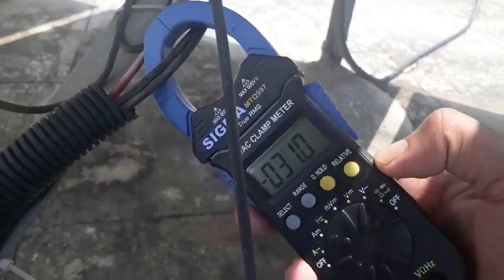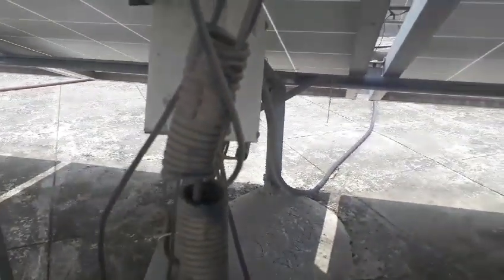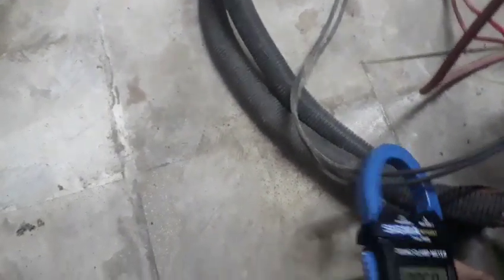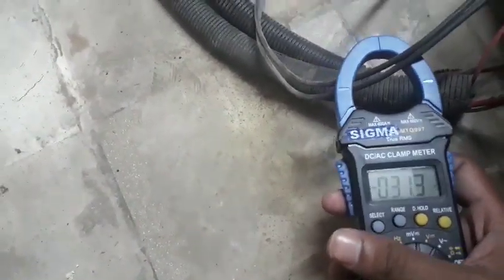The total parallel current generating is 30.6 ampere — this is the total current generating from the whole system. This is the off-grid solar inverter. These are the connections coming from the solar panels. The current generating from the solar panels is 31.2 ampere, as we have seen earlier.